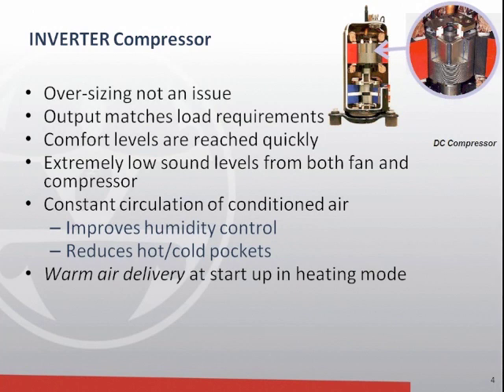The inverter in a ductless heat pump solves all of those problems. It's a sophisticated electronic control which actually causes the compressor, or in effect the engine of the mini split system, to operate just as the gas pedal on your car does. It ramps the system up and down to the exact amount of heating or cooling that's required, and it operates continuously instead of constantly cycling on and off. This gives you a whole bunch of features that are going to help us as we heat and cool our passive house. For one, oversizing is not an issue.